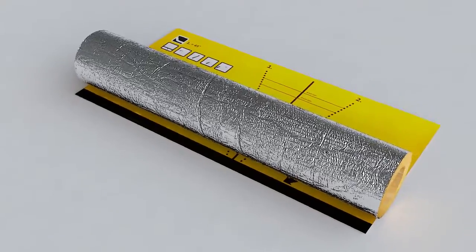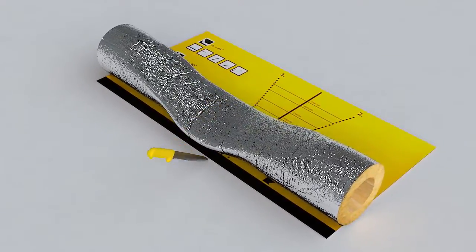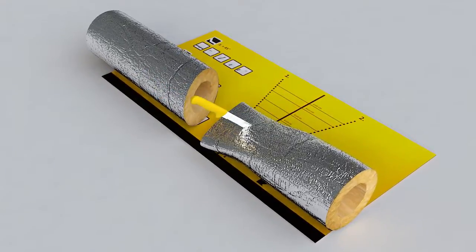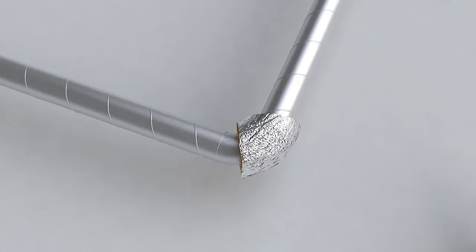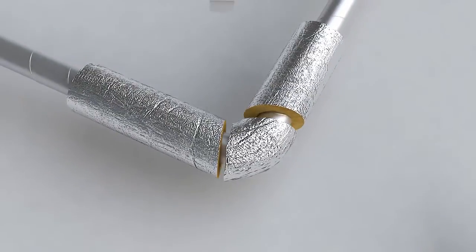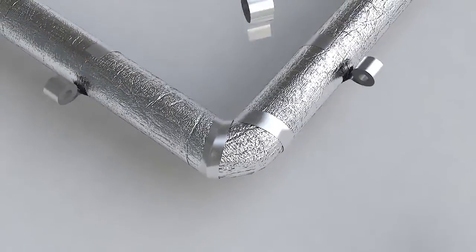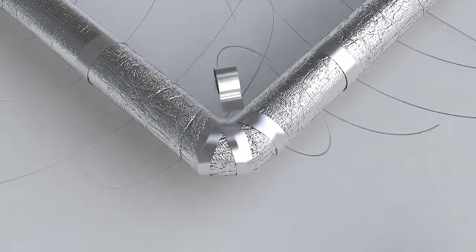When insulating a 90 degree angle, a separate angle piece is first cut from the product, following both of the packaging helplines. Then the corner piece is slipped into position and the remaining pieces of insulation are joined to it. Finally, the seams are taped and the insulation is firmly secured with binding wire.